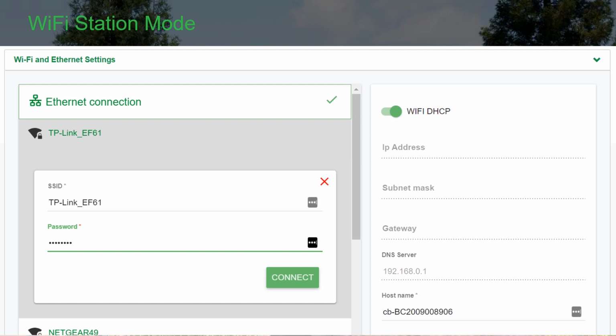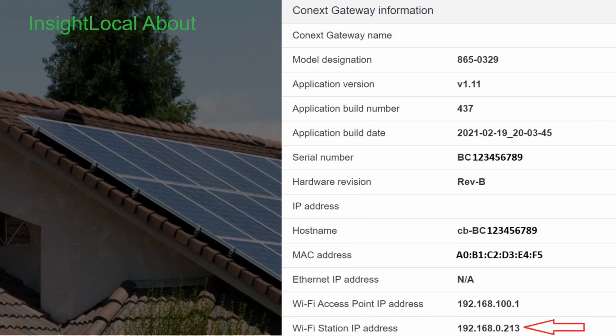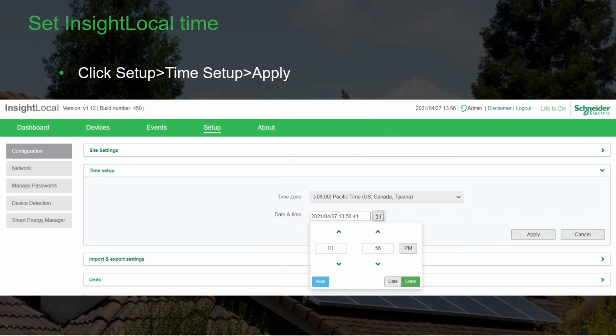If you previously had hardwired your router, remove the Ethernet connection and power cycle the Insight Local device. Then use a thumb drive to discover the IP address. Alternately, you can use Wi-Fi access point mode and then log back into the gateway web page. You'll be able to see the DHCP address assigned by your router in the About section. For security reasons, network time protocol was not implemented in InsightLocal, making it necessary to manually enter the date and time. If the date and time are incorrect, you will not have connectivity to Insight Cloud. This is the most common cause of Insight Cloud connectivity issues.